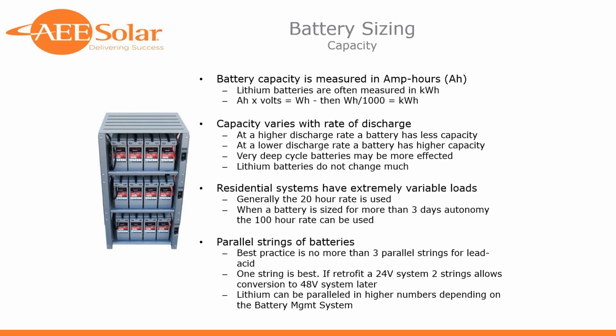So the formula is fairly simple for going from amp hours, which is generally what you're going to see for lead acid batteries, to kilowatt hours, which is generally what you'll see with lithium batteries. And I've gotten to the point where I just size all systems with kilowatt hours now, and then do a different calculation later to figure out what amp hour size lead battery I need.